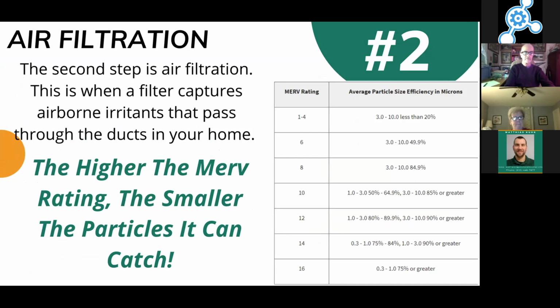The second aspect to IAQ is essentially air filtration. That is changing air filters, whether you have a 1-inch filter or some of these high-end filters. Clean filters are one of the easiest ways to maintain healthy air. Air filters are measured in a MERV rating. MERV stands for minimum efficiency reporting value. Essentially, it's a way to measure how big a particle a filter can remove out of the airstream. Most 1-inch filters, probably 75% of homes have 1-inch filters, are somewhere between a 1 and an 8 MERV rating.